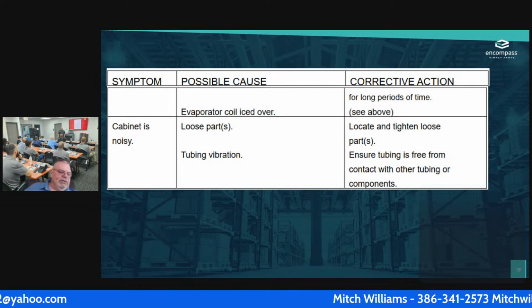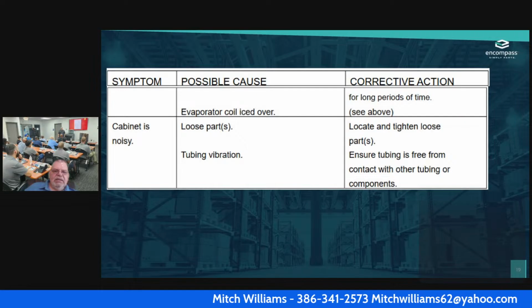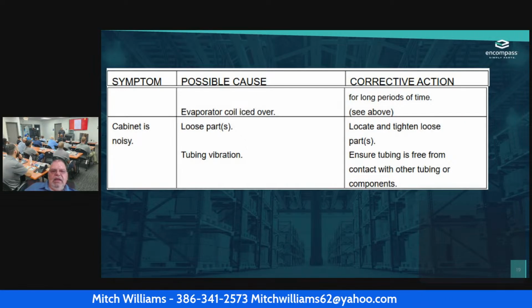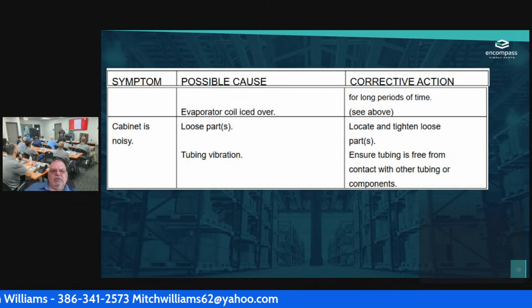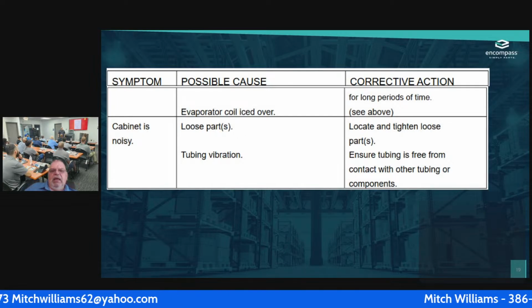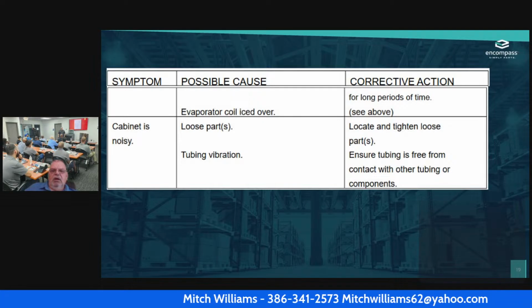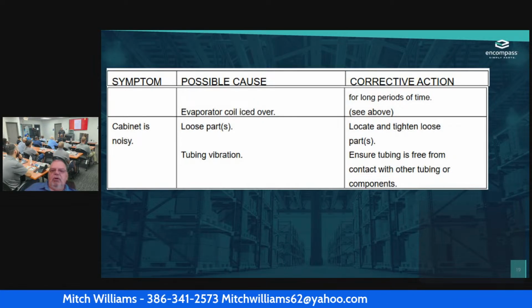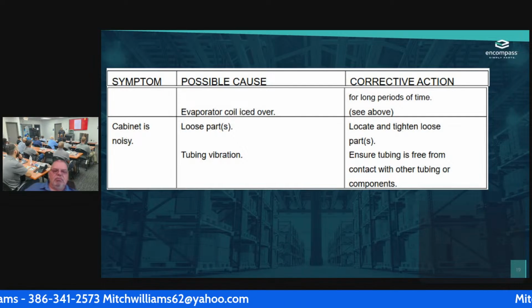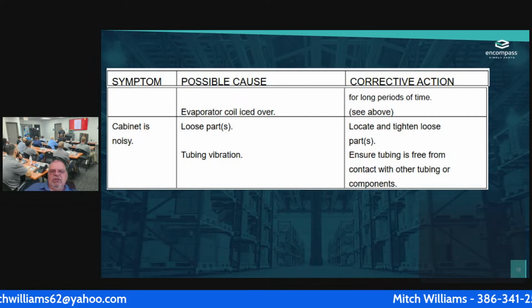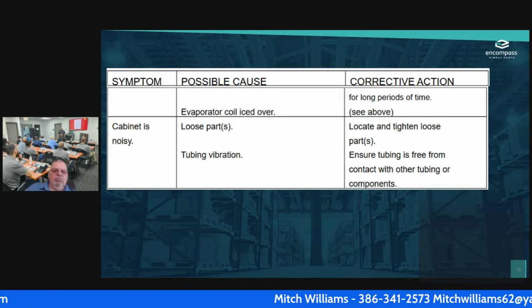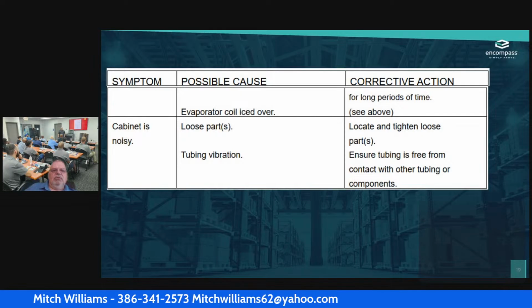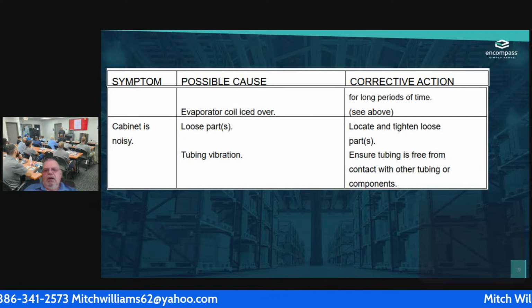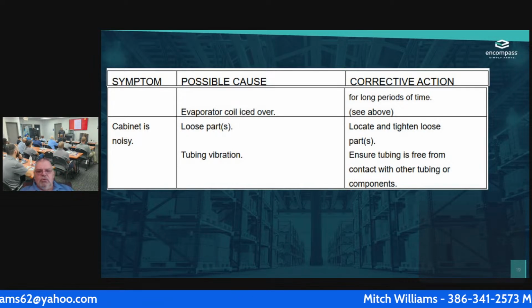So, cabinet too noisy. I did go out on one where 2 of the legs were over a drain, and that actually was causing the noise. But if I have a loose part, I need to locate and tighten that loose part. Usually it's a line that's vibrating. It could be the tubing vibration, so I may need to adjust that to make sure that it's working properly. So that is 2 of the things right there.